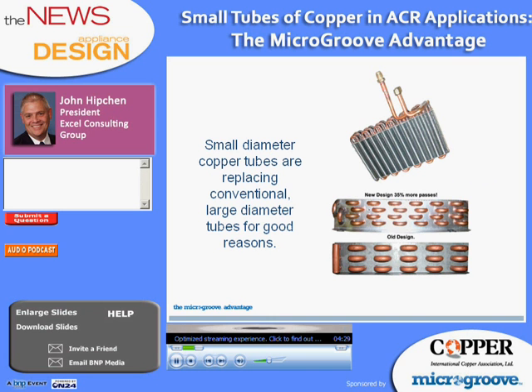This photo is taken out of a current catalog of heat exchangers, and it is a good example of the changes we're going to discuss today. The new design in this picture clearly shows smaller diameter tubes, and it not only provides 35% more passes, which will result in considerably more heat transfer, but you'll notice that the tubes are arranged in a staggered pattern, which will again improve the efficiency of this coil. And this is a good representation of the trend that we want to discuss today in more detail.